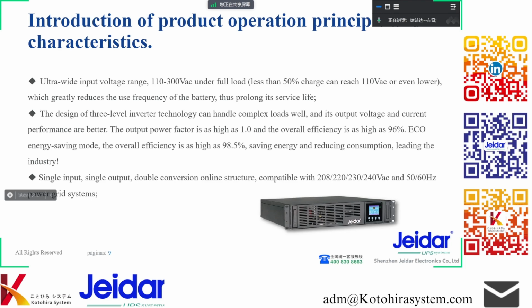Ultra-wide input voltage range 110 to 300 volts under full load. less than 50% charge can reach 110 volts or even lower, which greatly reduces the use frequency of the battery, thus prolonging its service life. The design of three-level inverter technology can handle complex loads well, and its output voltage and current performance are better. The output power factor is as high as 1 and the overall efficiency is as high as 96%.